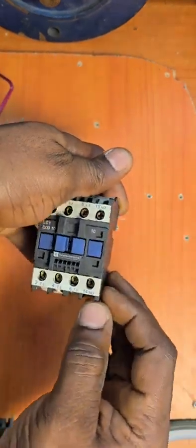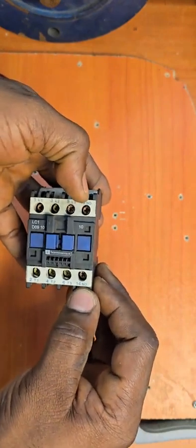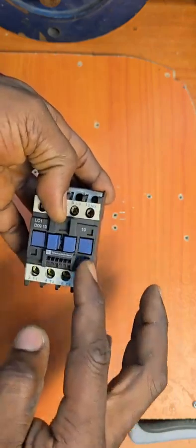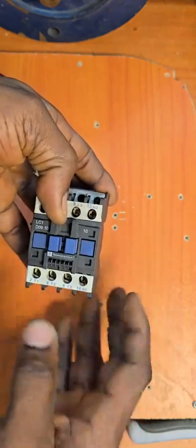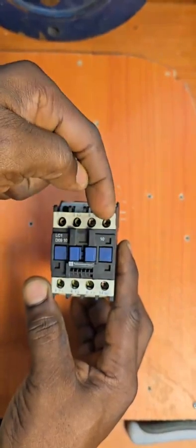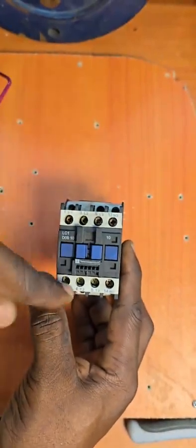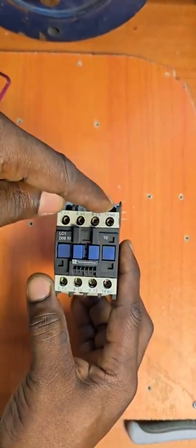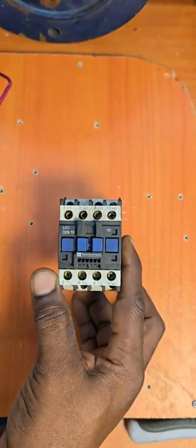And then, of course, on this line you're going to have your 13NO and 14NO. This is normally open. So this contact here is open until this contactor is energized. So this is another auxiliary contact. It is not 4 here, it's only 3 for power, and then this for control, which is the auxiliary terminals.